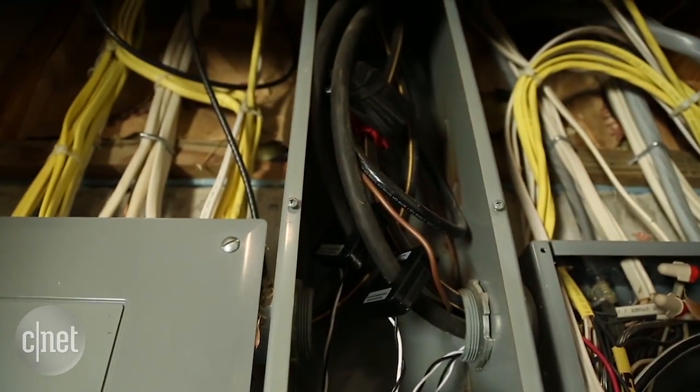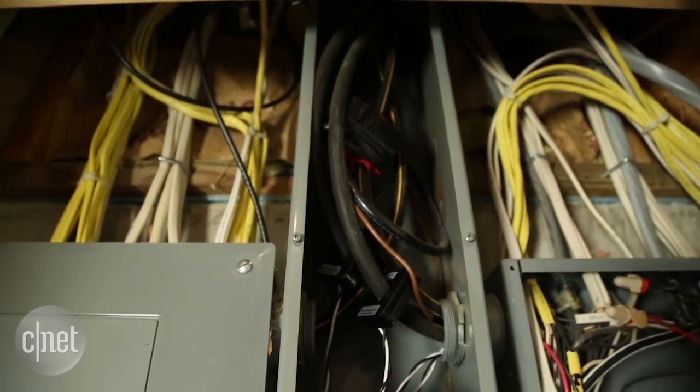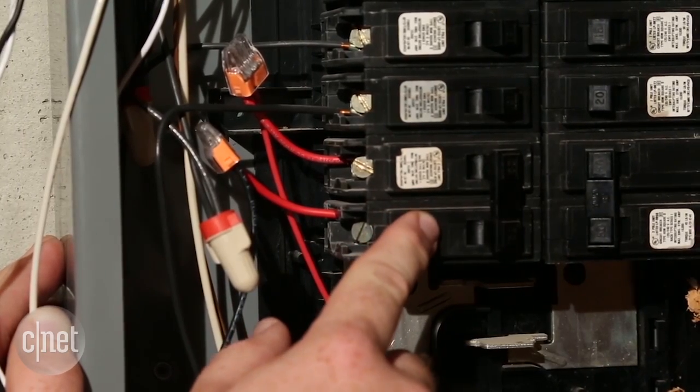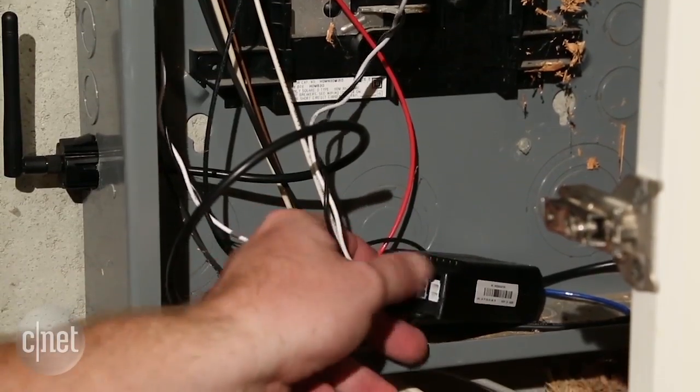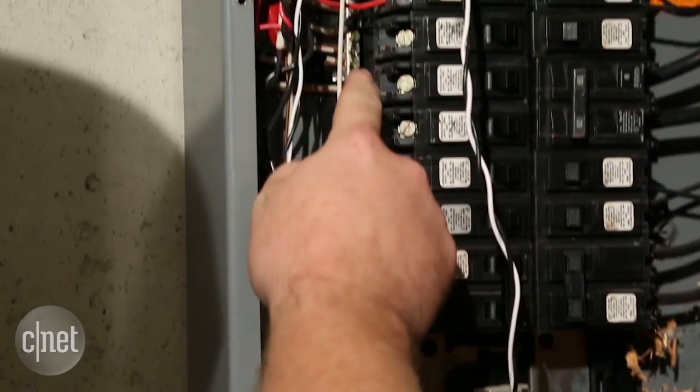The first step is to identify the two different phases in your box. You can see that we wired into each one of those phases on our double pole breaker and ran that back to the main Neurio device. After that, the Neurio device also has a white neutral wire — run your white wire from the Neurio device to the breaker bar and install it there.